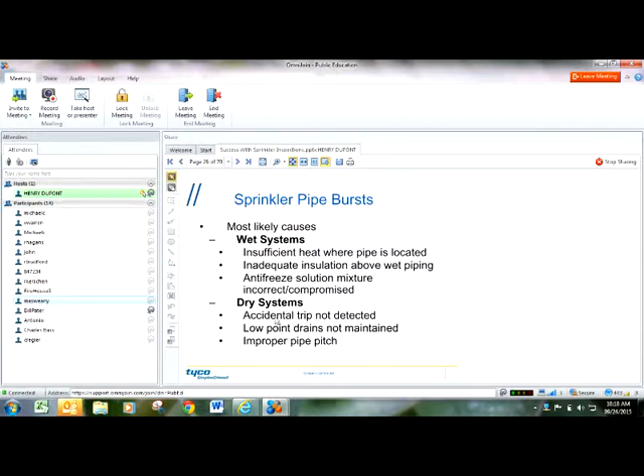On dry pipe sprinkler systems, accidental trips not detected, or if you have a trip in the summertime of your dry system and the water is not all purged out correctly, then that wintertime rolls around, that freezes and breaks. This is a biggie. Low point drains are not maintained. We're going to talk about that here in a couple slides. And then another biggie is improper pitch on dry pipe sprinkler systems. As I stated earlier, you have to have pitch on your sprinkler system.